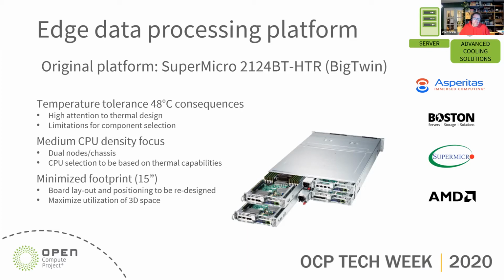When I state 48 degrees C, we're now already with the same platform at levels of 50, 51 degrees C cooling. We call this a medium CPU density focus - there's still a lot of CPUs, so if we look at the space we're utilizing, the density is pretty high, but we're not talking about the highest TDP specs in this case. The CPU selection has occurred based on the thermal properties and capabilities of the CPUs.